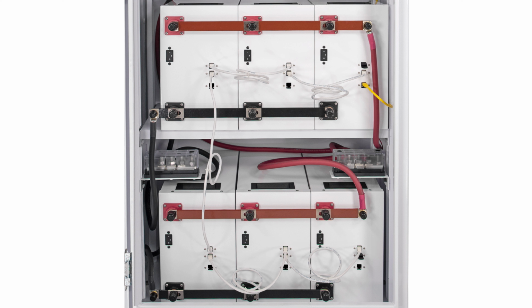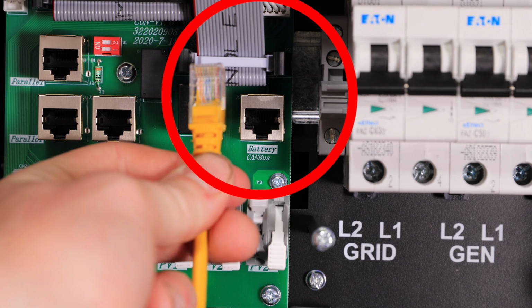Last, using the included yellow Ethernet cable, connect only one battery in the bank to the Sol-Ark inverter. This cable will connect the port labeled device on the battery to the port labeled battery CAN bus on the inverter.